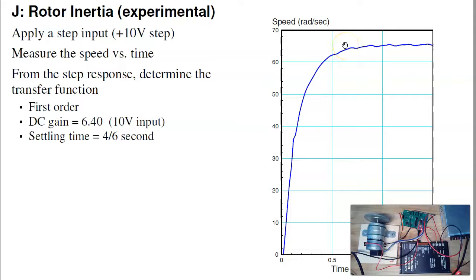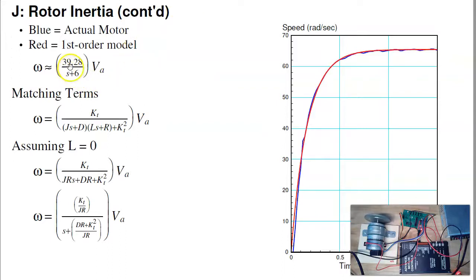From this, that really looks like a first order differential equation. That's the step response of a first order system. You know, no overshoot, a nice clean response. I can come up with a first order approximation for that. To do that, I would say the DC gain is roughly 6.4. This goes to 64 radians per second. I've got a 10 volt step input. So 64 over 10 is 6.4, your DC gain. The settling time is about 4/6 of a second. That tells me the dominant pole is right around minus six. So what I can do is take a first order approximation that has the same DC gain, same dominant pole. Plot the step response of that first order system, that's the red line, compared to the actual motor. And you see that the two are pretty darn close.